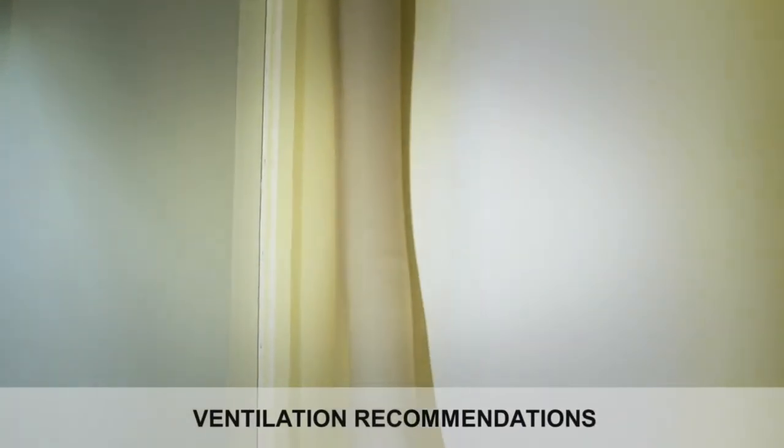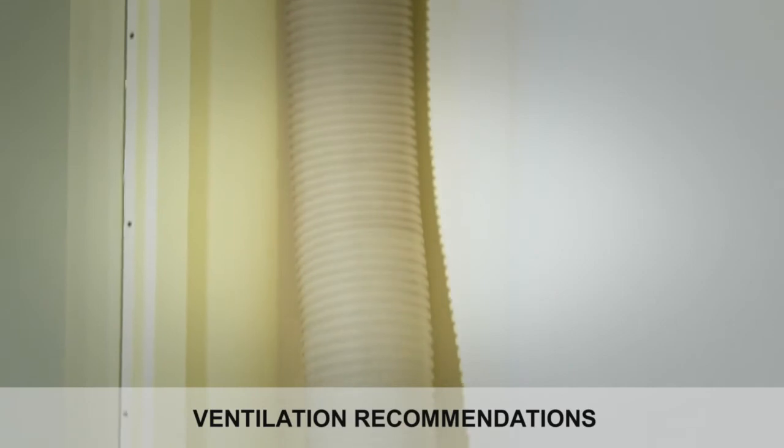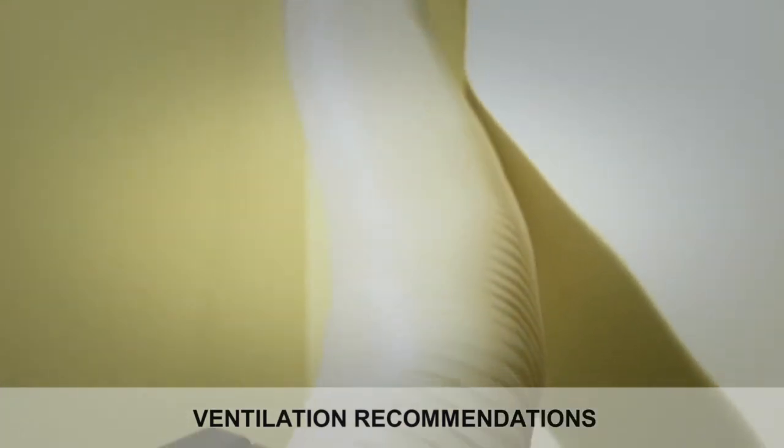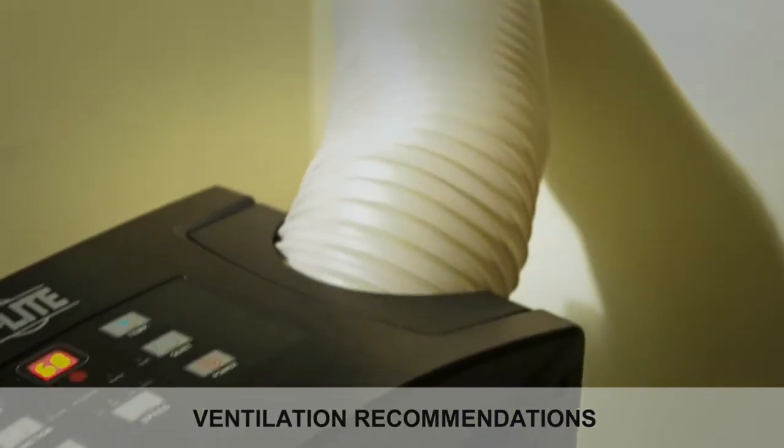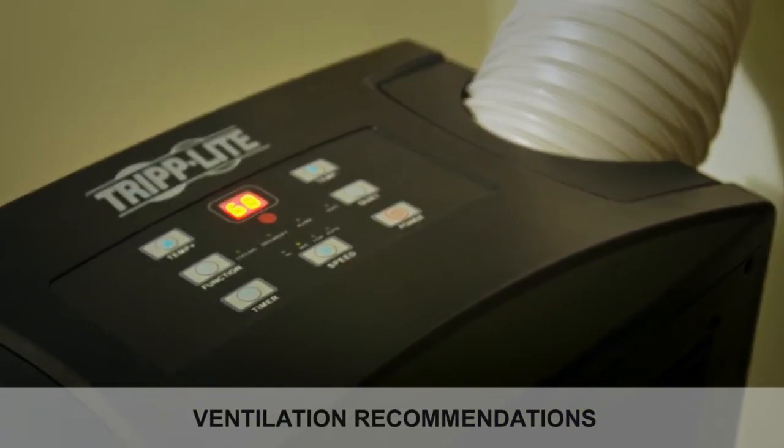To ensure optimal performance and ventilation, the exhaust duct should be connected to the space using as straight and short path as possible. Do not allow the duct tube to bend between the unit and exhaust area. The exhaust area should be at least 10 inches deep to provide adequate ventilation.